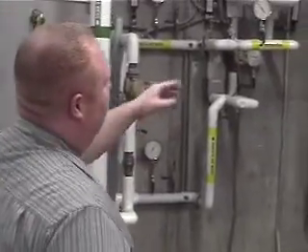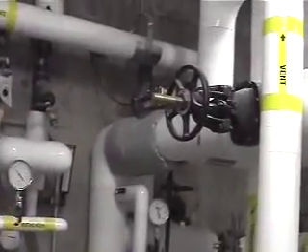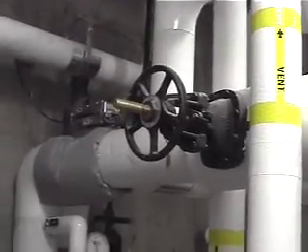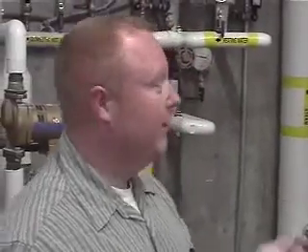To start with, we're in the mechanical room down in the hot water system looking at the heat exchanger. We're going to start in the back of the room and kind of go forward. This valve right here, obviously, you guys know, is your isolation valve. This is tied to two different things. It's tied to that emergency switch on the wall right there, so if there's an emergency, shut that. It fails closed. And also, if you disable the system, that steam valve will close as well, and you can also close it in software as needed.